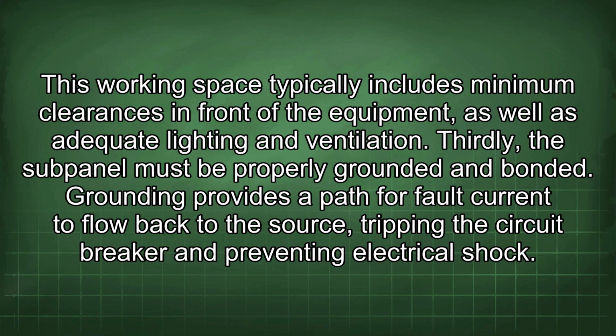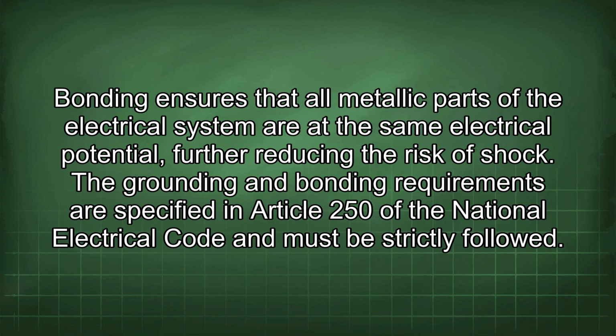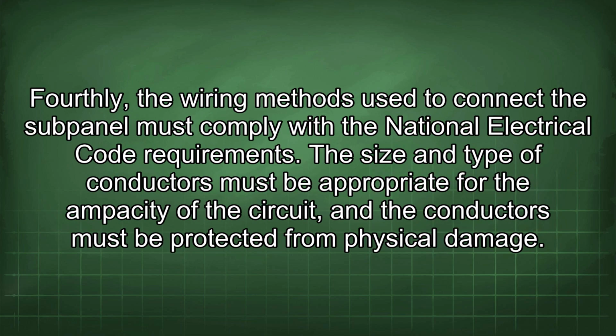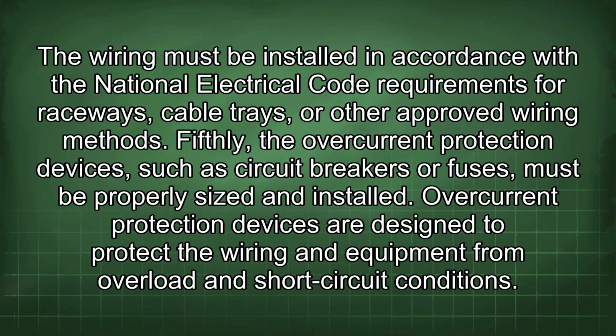Thirdly, the subpanel must be properly grounded and bonded. Grounding provides a path for fault current to flow back to the source, tripping the circuit breaker and preventing electrical shock. Bonding ensures that all metallic parts of the electrical system are at the same electrical potential, further reducing the risk of shock. The grounding and bonding requirements are specified in Article 250 of the National Electrical Code and must be strictly followed. Fourthly, the wiring methods used to connect the subpanel must comply with the National Electrical Code requirements. The size and type of conductors must be appropriate for the ampacity of the circuit, and the conductors must be protected from physical damage. The wiring must be installed in accordance with the National Electrical Code requirements for raceways, cable trays, or other approved wiring methods.